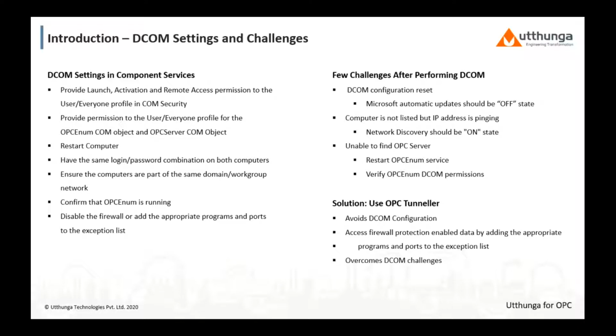conditions need to be maintained, like you have to have the same login password combination on both computers, and you have to ensure the computers are part of the same domain or the same workgroup network, and you have to confirm that OPC Enum is running, and you have to disable the firewall, or if not, you need to add the appropriate programs and ports to the exception list so that the firewall will not block.